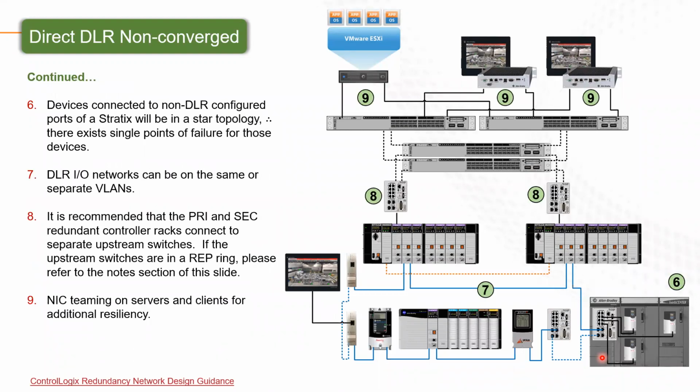And let's see, again, number 6 is typically how we would do one of our MCCs. It is usually a star or linear network inside the MCC bucket. Then we will use the 5700 switch in the MCC as a connection to the ring. We typically will use 2 switches when we do a redundant ControlLogix, one for each NIC card for our redundancy and self-healing.